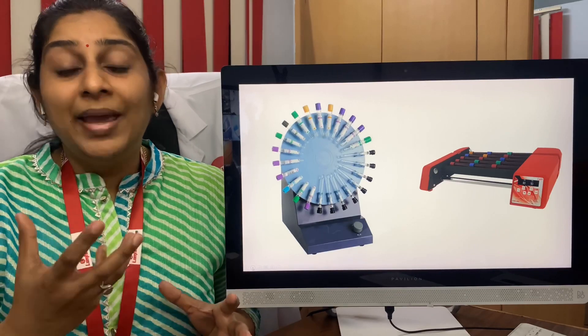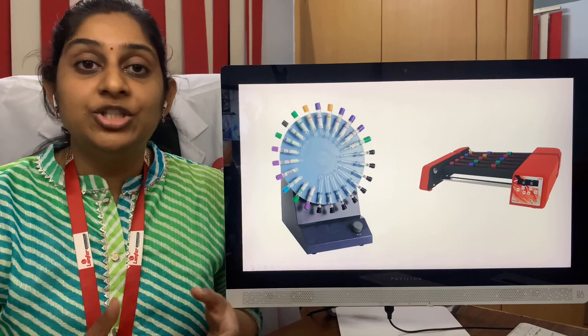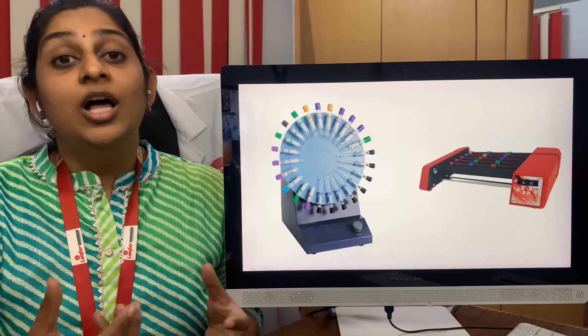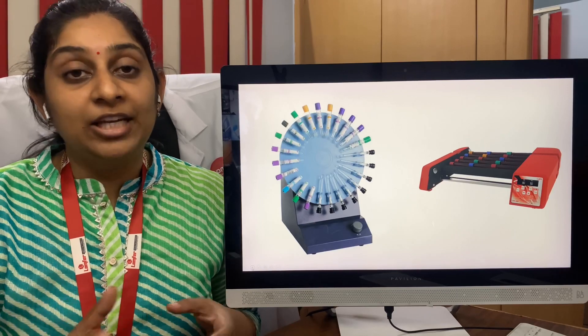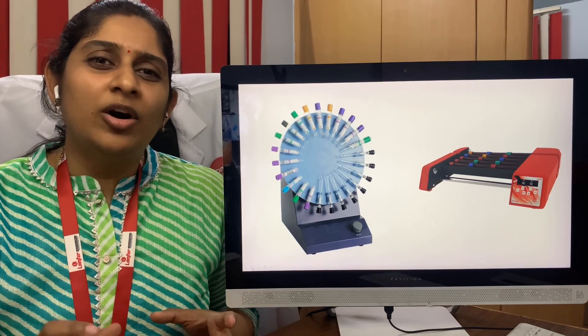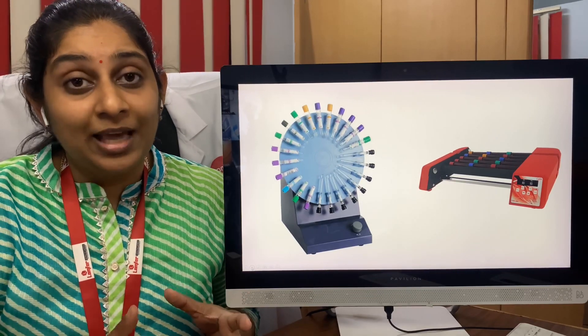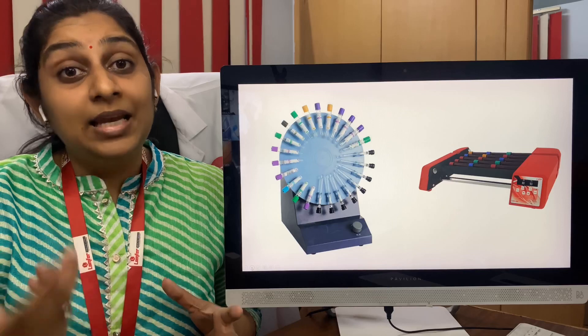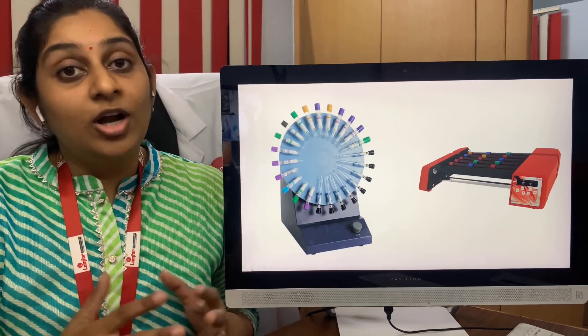The main purpose of having a blood mixer is that when a technician shakes the sample tubes containing the anticoagulant, sometimes they shake it too vigorously or inadequately. The blood samples may not be properly mixed with the chemical, or the sample gets lysed due to vigorous shaking. When you use a blood mixer, that won't happen and you get even distribution of blood mixed with the chemical.